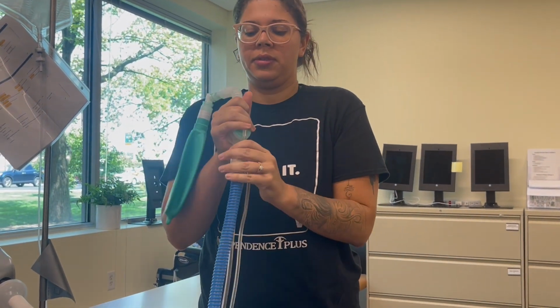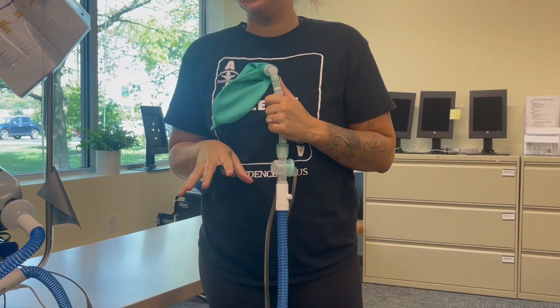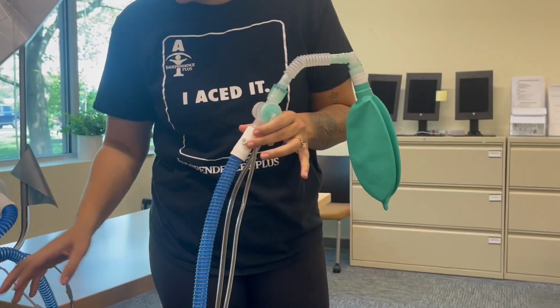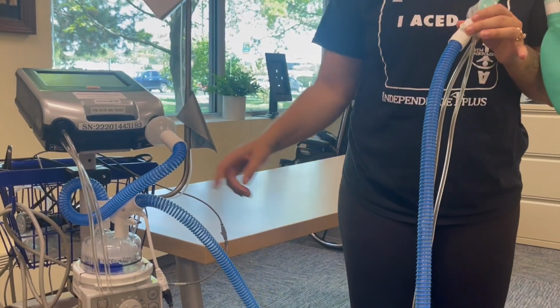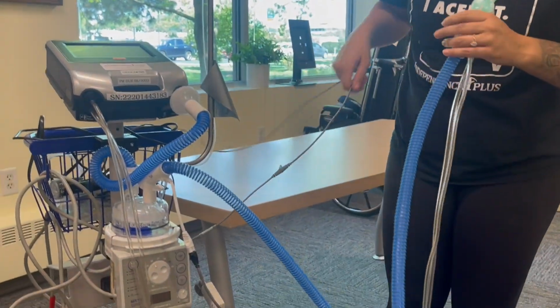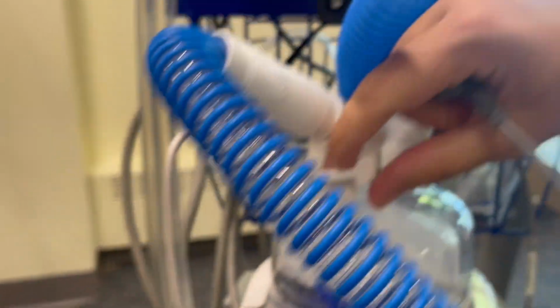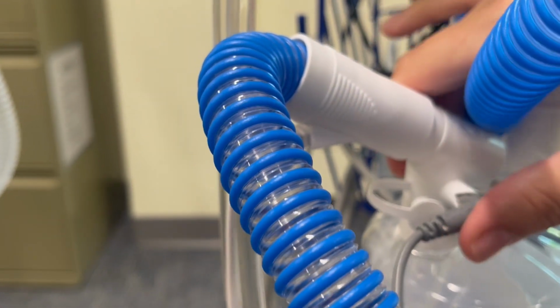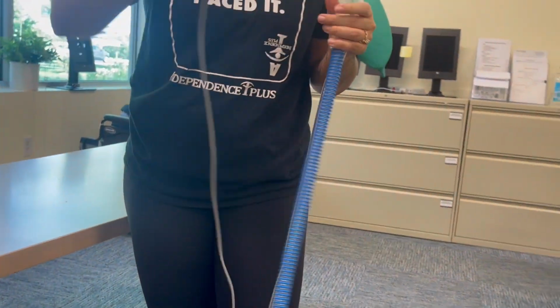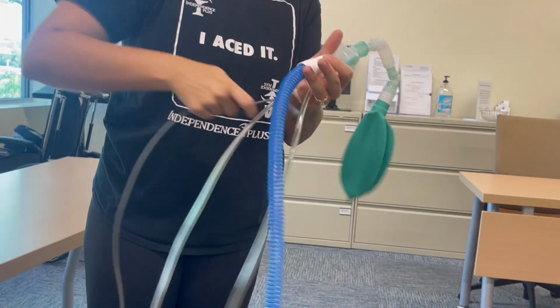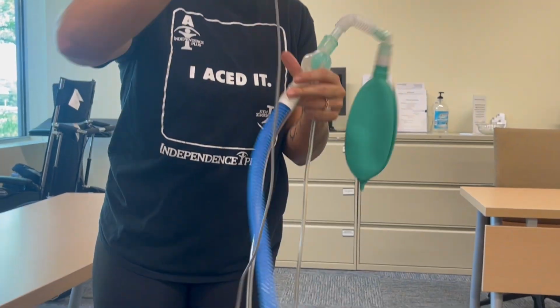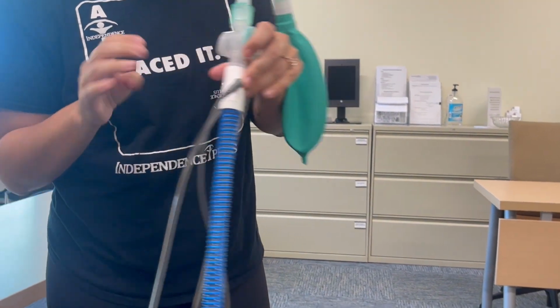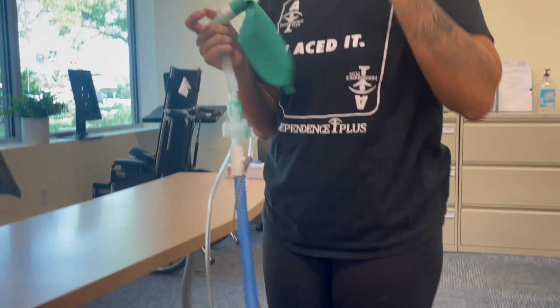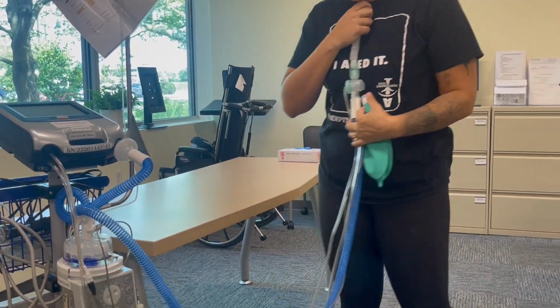My dead space is going to get connected to my exhalation valve. So the last thing that I need to do, my circuit is almost fully complete, but I do have my heater wire probe sites open. And if I don't connect my heater wires here, this will cause a really big leak in your circuit. So here are my heater wires, and I have a short probe. This short probe is gonna actually connect into here. And then I have a long probe. Some people like to coil this around the tubing. You don't necessarily have to do that, but you can. And then this long probe is just gonna connect into here. So now, if I wanted to turn on the astral vent, I could turn it on and connect my patient to it, and I'd have my completed circuit.